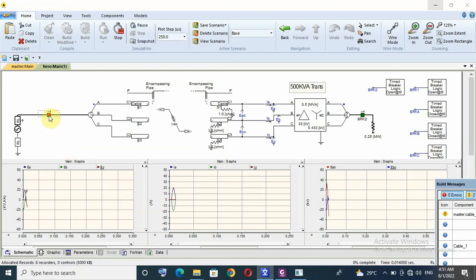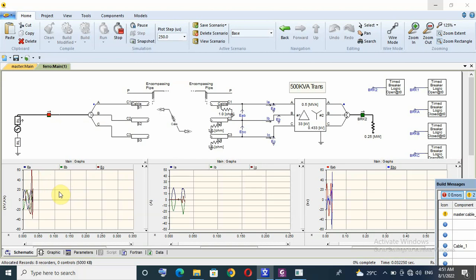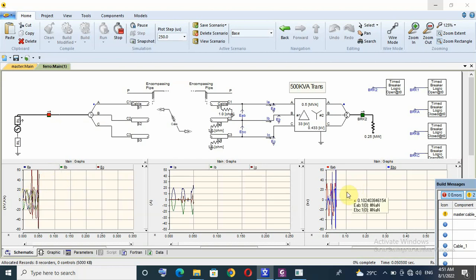Here we have like fuse, just single phase, single phase operation. That means from start, I lose one phase, C phase, as you see here in this graph for voltage to earth, line to earth voltage here. It should be 19.05 kV, and here line to line voltage, and here transformer current.